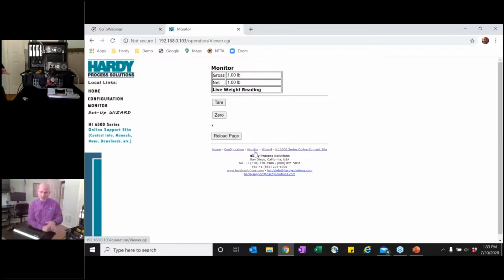weighing pallets, I've got my forklift on the shipping side of my factory, and I'm just taking a pallet and laying it on a floor scale to make sure I have the right number of cases in that pallet. This reading is probably fast enough. But if I'm in the dispensing area where I'm feeding by rate, if I'm that slow, I'm going to overfill or underfill, and I'm going to slow my process down. So we have the accurate, we have the stability, but we don't have the fast. So let's go back and see what we can do about that.